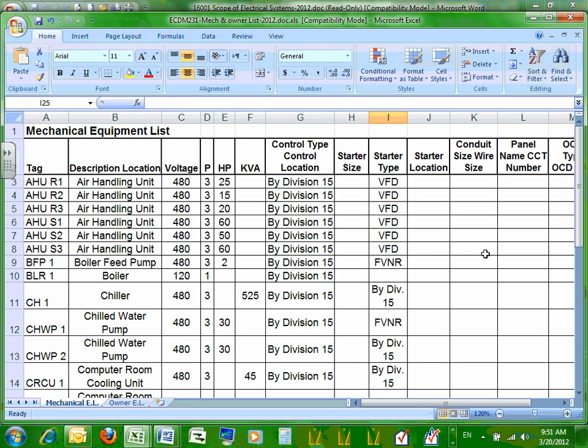But if we have a number of VFDs in a project, we would model the electrical system, including the VFDs, in our power tools analysis, and we could look at the harmonic impact of the VFDs at different components, and we could then perhaps require a line reactor to help minimize the harmonic feedback into the system. But if it's really intense in a certain area, because we've got a bunch of VFDs off of this big distribution panel, and they're big VFDs, we may need to have a tuned harmonic filter.